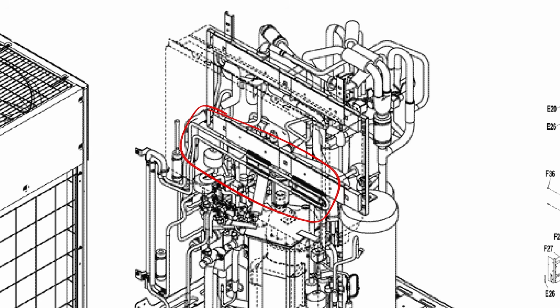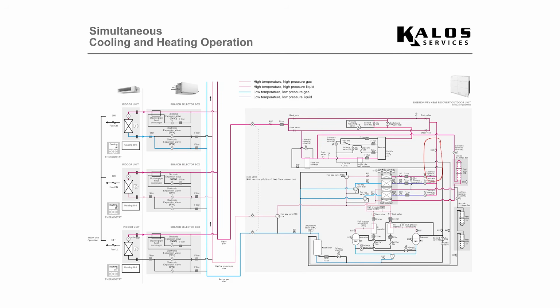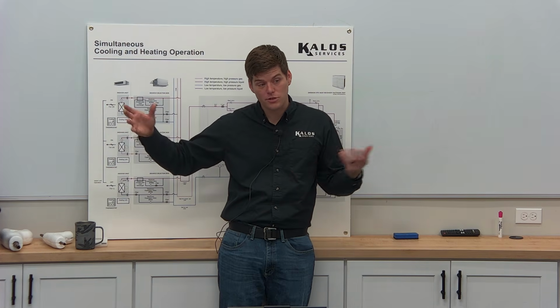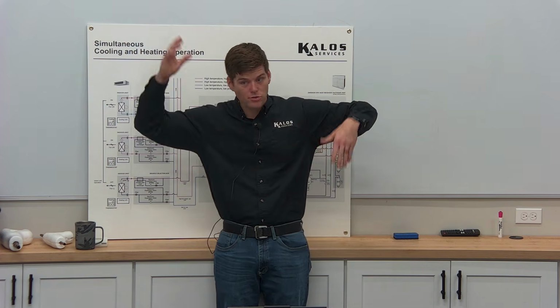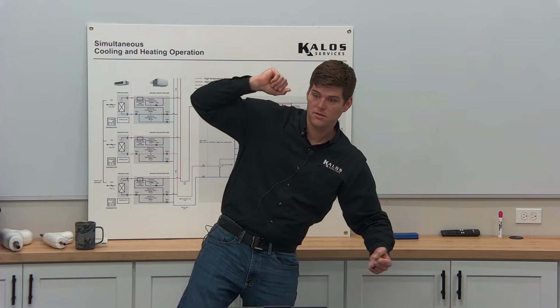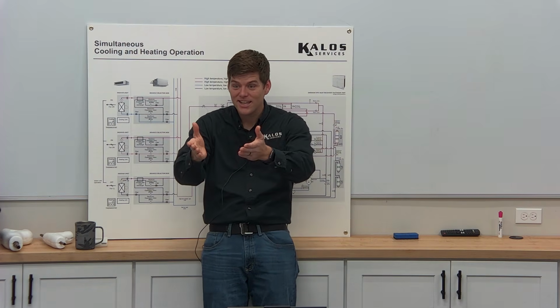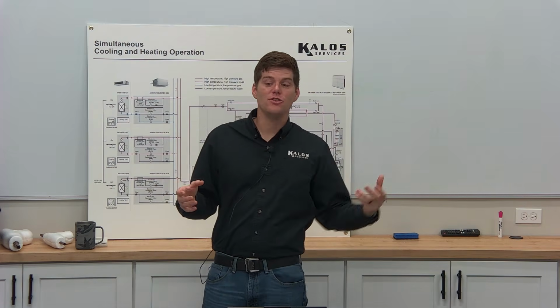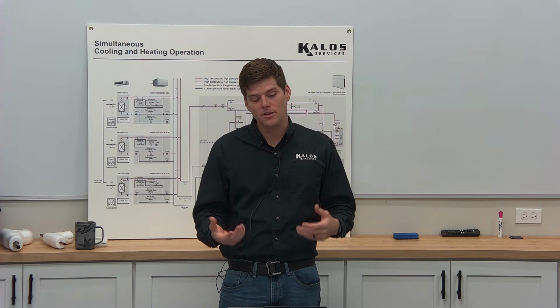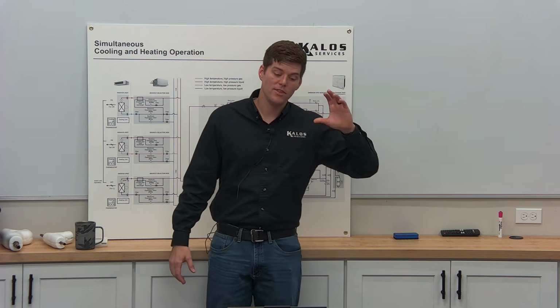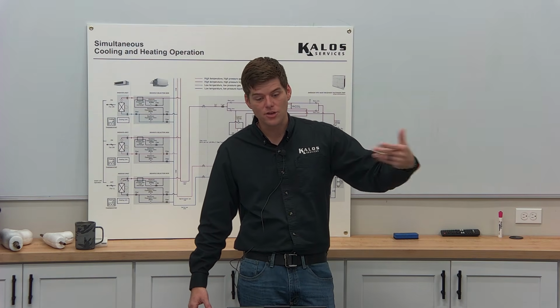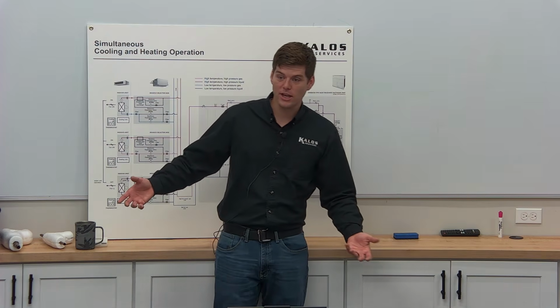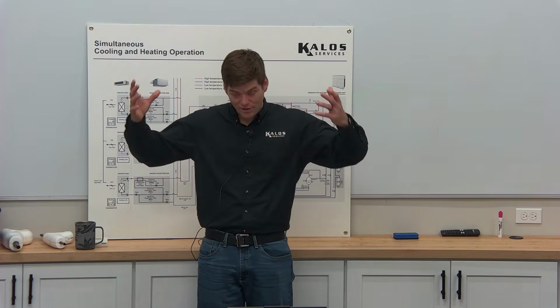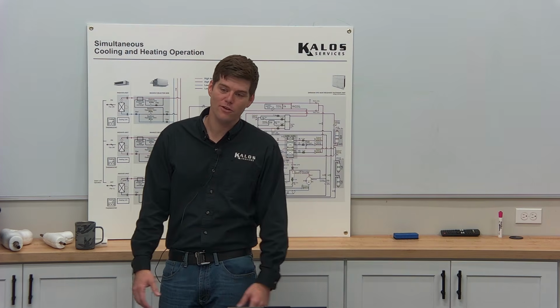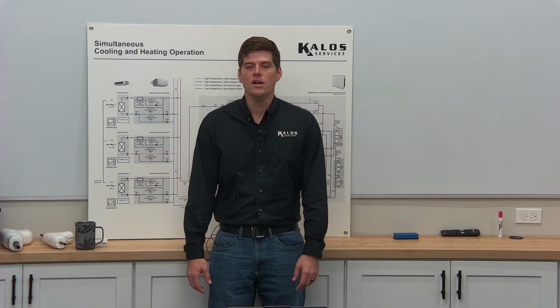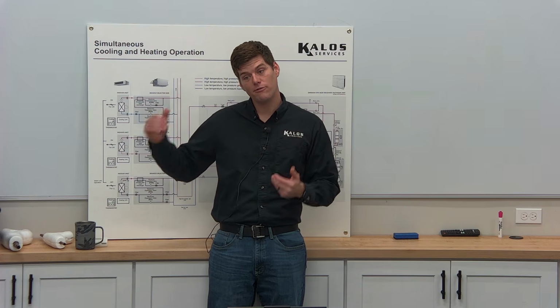When we take AC voltage and we convert it to DC voltage and then we trickle it through pulse width modulation to our compressors and our fan motors, because they're both DC voltage driven, they're both pulse width modulation, they both have a bunch of different speeds. It generates what? Anybody? Heat. It generates heat. Back in the day, they used to be air-cooled inverter boards. They used to go to a heat sink, and then air would come across them, but then they found it was a very archaic way to do things because these heat exchangers inside the outdoor unit, when it's 110 degrees in Arizona, and you're in cooling, and you're moving that 110-degree air from the actual outdoor heat exchanger across these fins, it just overheats the inverter boards, and they die prematurely because of overheat. So they changed it to actual using liquid refrigerant to cool the boards.